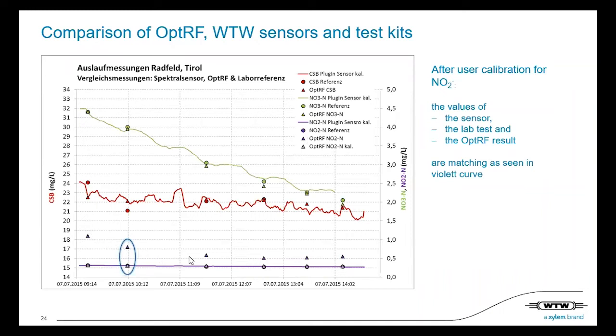And if you look after the user calibration, when we did a routine measurement with the nitrite test kit in the lab, and then compared the raw values and entered them versus the measured values, we have an absolute adjustment of the lab values with the optical reagent-free values.